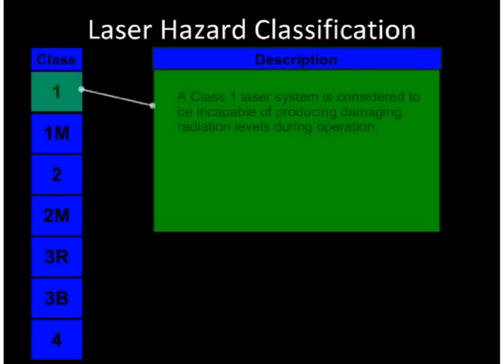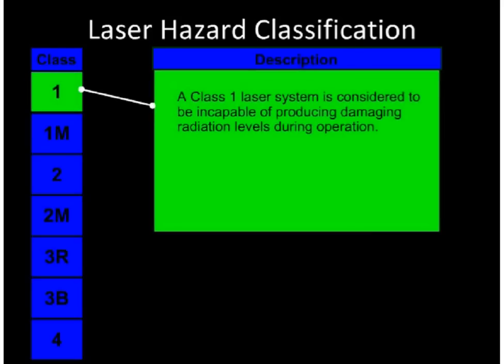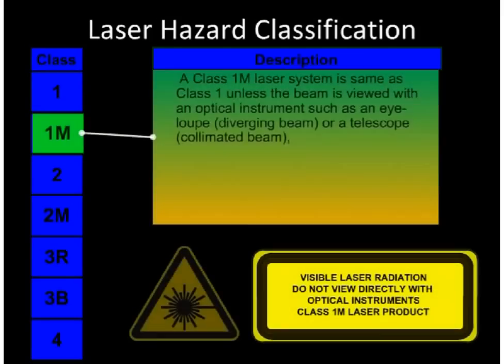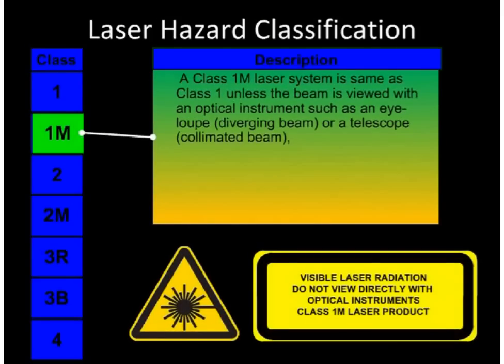Laser hazard classification. A hazard classification scheme is used to define a laser's potential to cause an injury to the eye or skin. Class 1 is not considered capable of causing an injury. Class 1M is not considered capable of causing an injury except when viewed through specific types of magnifying optics such as a hand magnifier or telescope.